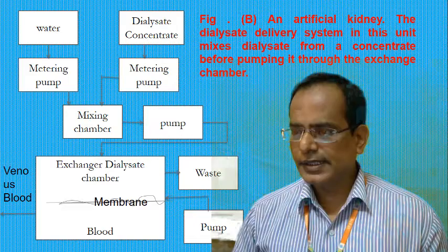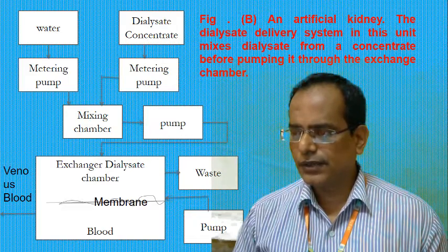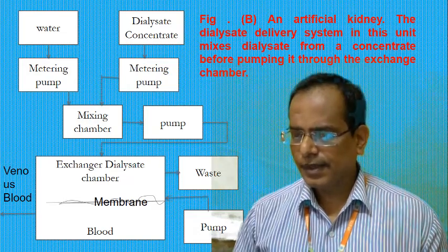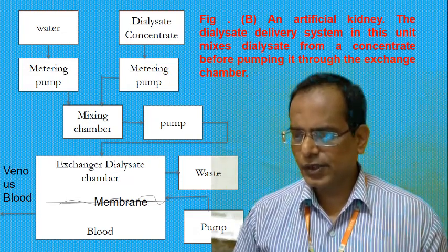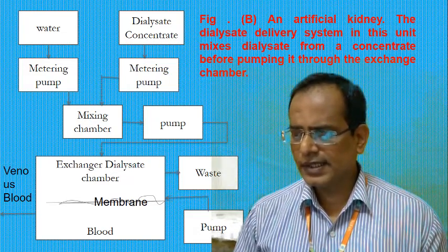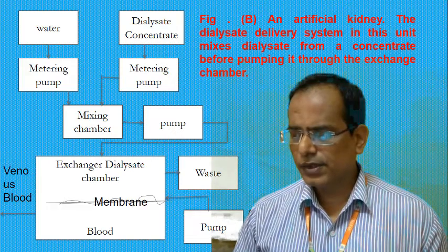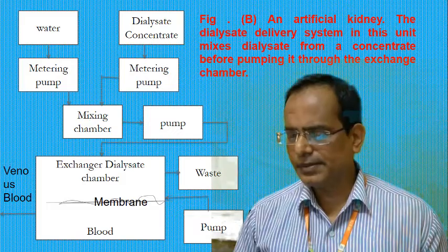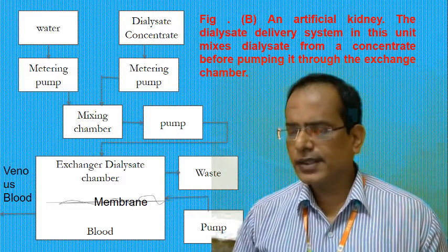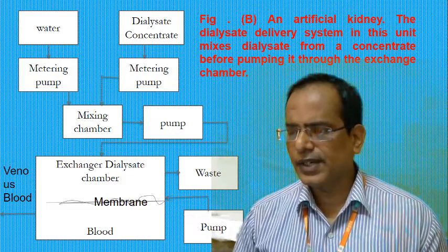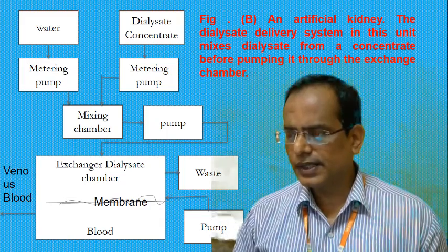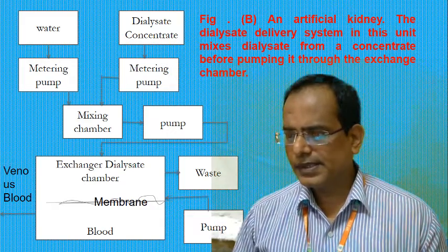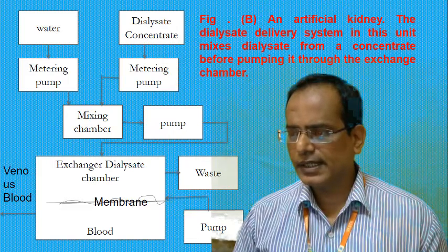However, the increased pressure improves the ultrafiltration rate of a membrane, and it is important in this unit that the dialysate also be forcefully circulated to ensure rapid mixing, because fresh dialysate must be available at the surface of the membrane through the coil. A pump is necessary for the dialysate as well.